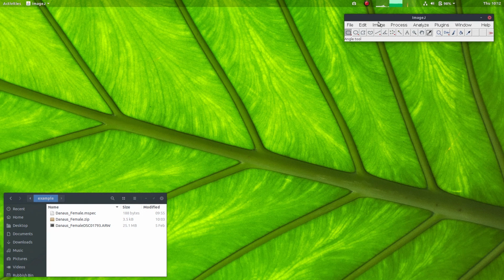Image exposure is a really important thing when creating calibrated images. If an image is overexposed, any parts of the image that are overexposed have reached the saturation point of the sensor, so the sensor can't go above its maximum value, and it effectively cuts off any pixel values above that, and it can create very misleading results. So an image with overexposed parts cannot be used.